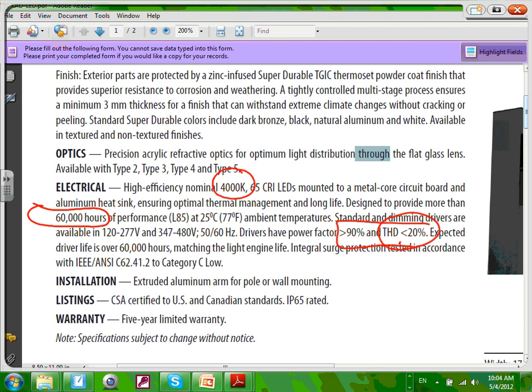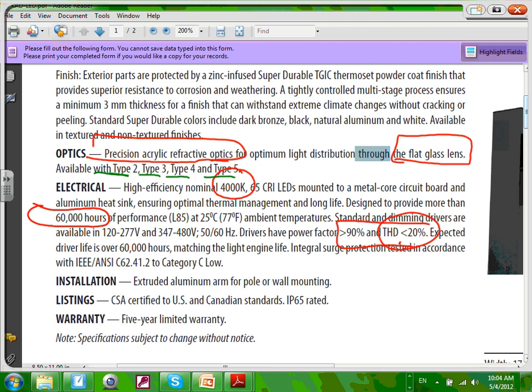They have refractive optics for optimum lighting distribution and flat glass lenses — exactly what we were just talking about in terms of reflectors. The type of distribution for parking lots matters — type 2, type 3, type 4, and type 5. These determine whether the light is shooting forward, horizontal, or backward. The type of distribution for the fixture is a big deal, especially for parking lots. You can see how if you want 100% cutoff you have to specify a certain type.